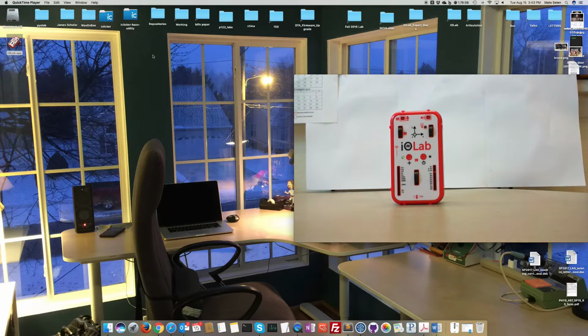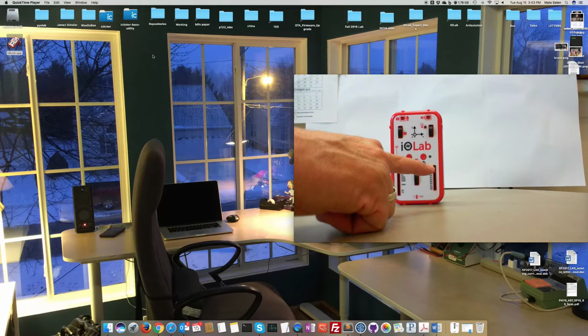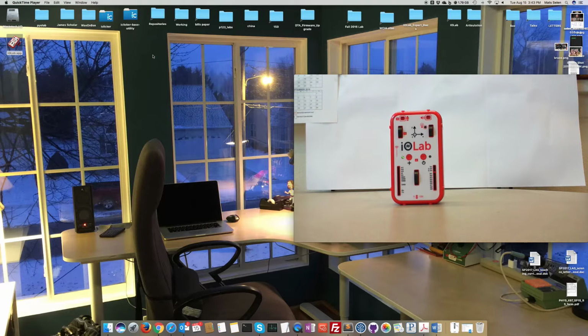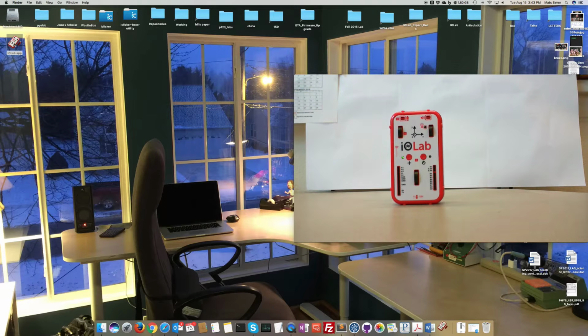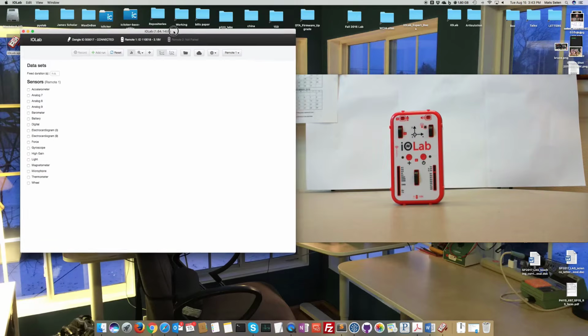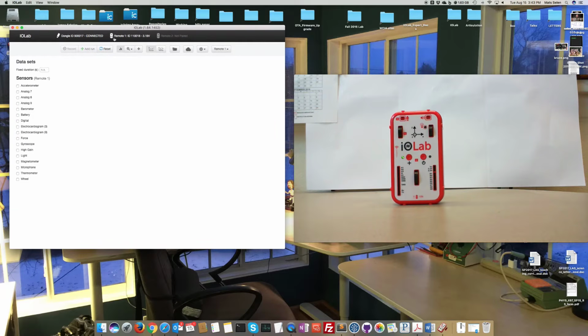And you can tell that the device is on because the lights are flashing, and you can tell that this thing is paired with the dongle because the lights flash left, right, the way they do. Okay, so let's start up the software. There it is. Now, the status bar on the top here tells us that the dongle is plugged in and is connected, and that the remote one, that is the device over here, is turned on, and the battery voltage is over 3 volts, so they're brand new batteries.